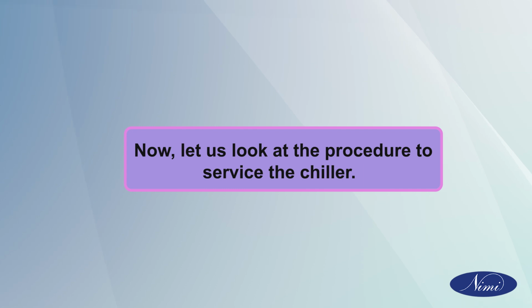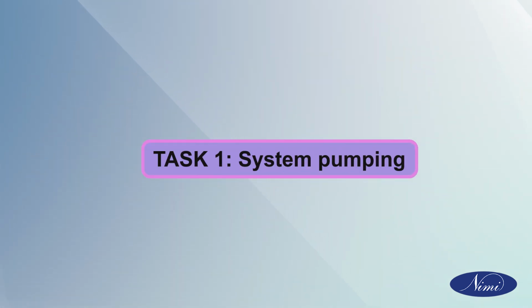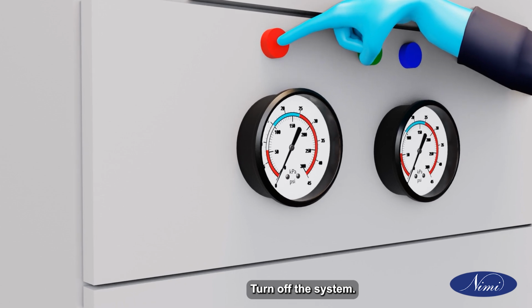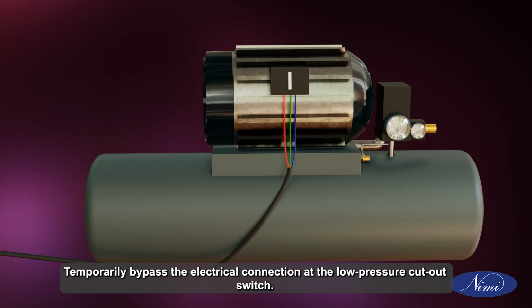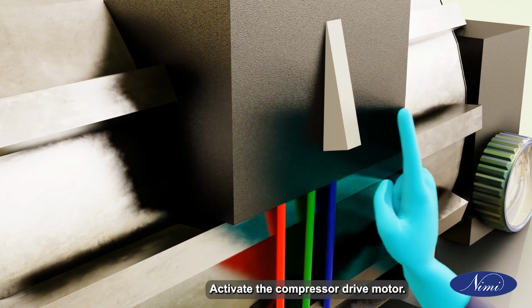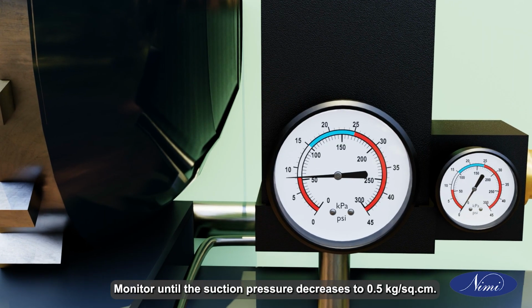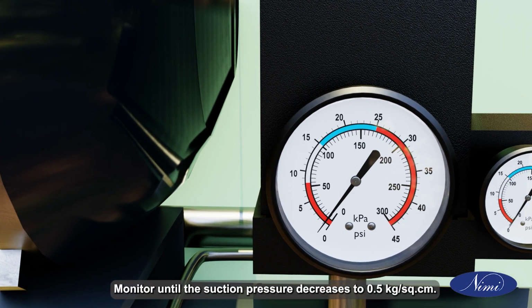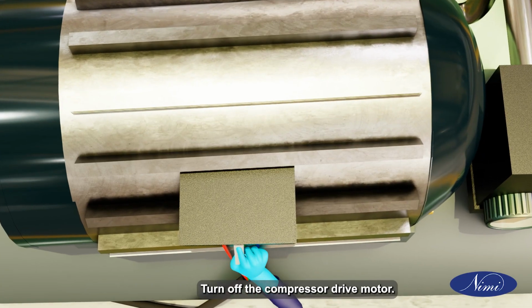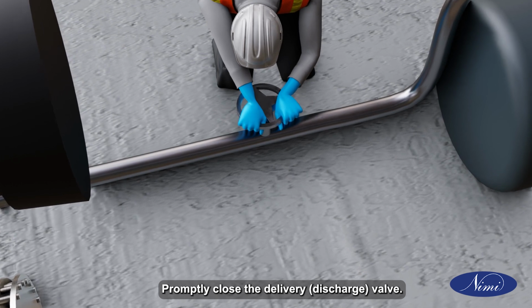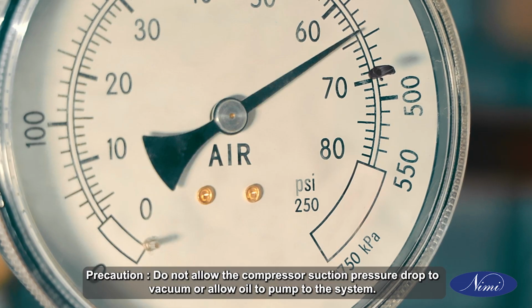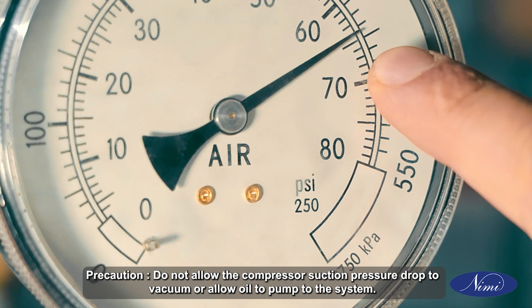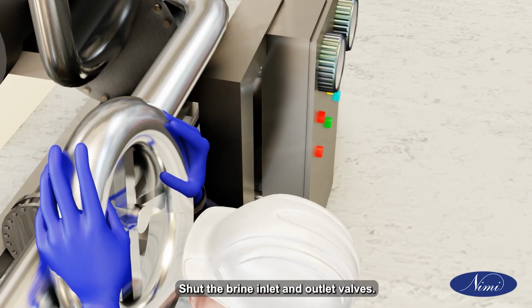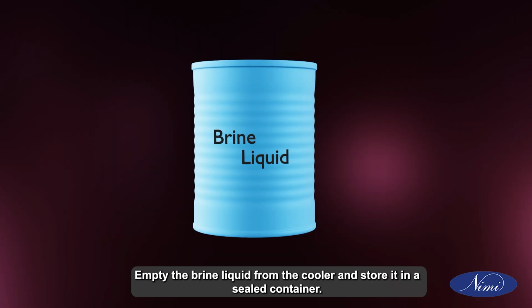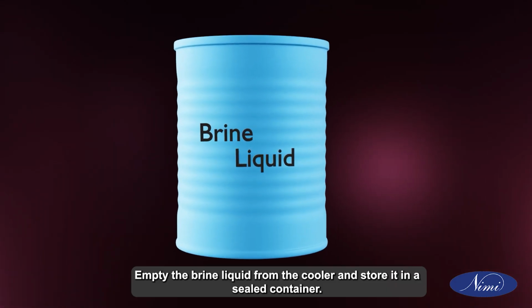Now, let us look at the procedure to service the chiller. Task 1. System pumping. Turn off the system. Shut the liquid line. Temporarily bypass the electrical connection at the low pressure cutout switch. Activate the compressor drive motor. Monitor until the suction pressure decreases to 0.5 kg per square centimeter. Turn off the compressor drive motor. Promptly close the delivery discharge valve. Precaution: do not allow the compressor suction pressure to drop to vacuum or allow oil to pump into the system. Shut the brine inlet and outlet valves. Empty the brine liquid from the cooler and store it in a sealed container.